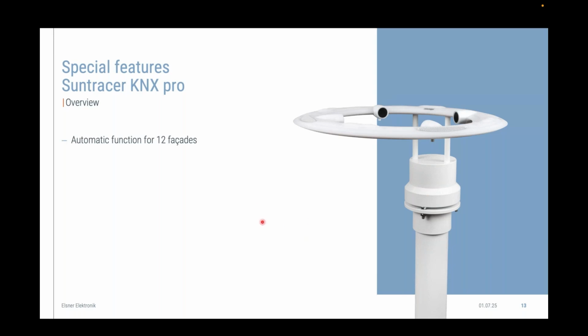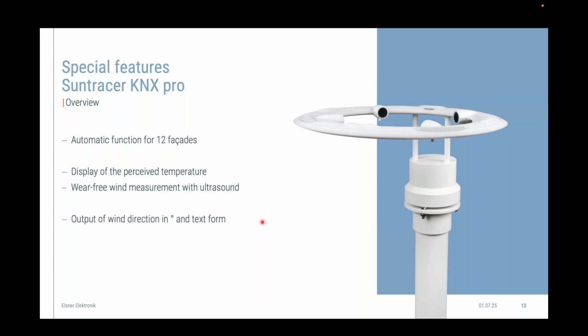Okay, the special features of the Suntracer KNX Pro. As mentioned before, we can automate 12 facades. We can display the perceived temperature via KNX. The wind measurement is wear-free with ultrasound. The output of the wind direction is in degrees and text form, as well as the air pressure in hPa and text form. And if you have a closer look at the parameters in the ETS, you can see that many values are sent in text form. So it's perfect for a building management system to get the different texts. The programming is via magnetic push button.